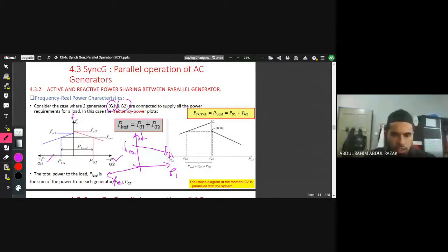It might have a different droop level because the frequency at no load might be at different values, because not all generators come with exactly the same parameters. It has to have some sort of difference, but later during operation you have to regulate such that both are emitting the same parameters in terms of voltage, frequency and phase. Initially, especially when we buy from different manufacturer brands, for sure they come with a different level in their house diagram.